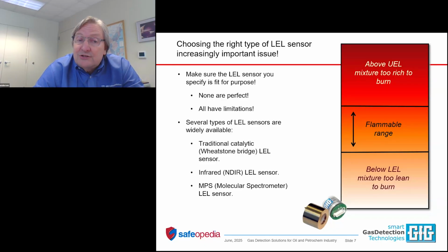The most common is still the traditional catalytic Wheatstone bridge type sensor. These sensors detect the gas by oxidizing the gas. With oxidation, you take a little more power. You have a bead that's heated to a high temperature in the sensor. In the presence of gas, the bead increases in temperature because of the oxidation or burning on the actual surface and inside of the bead.